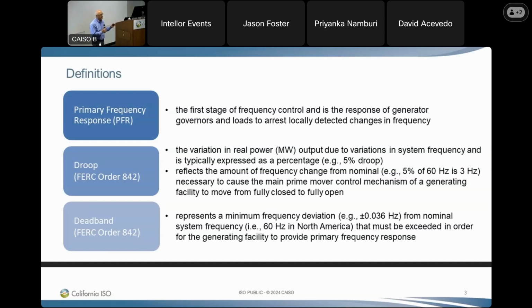But if you take a step back and look at a traditional thermal unit that's operating on a system, there's a magnetic bond that is in place between that unit and the interconnection. And if the frequency of the interconnection were to drop, that magnetic bond would automatically make the generating facility produce a little bit more energy and put it into the grid.